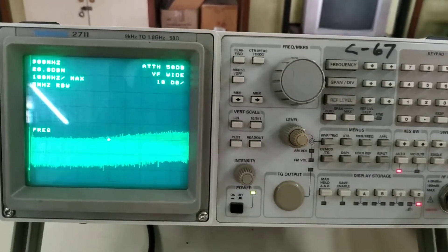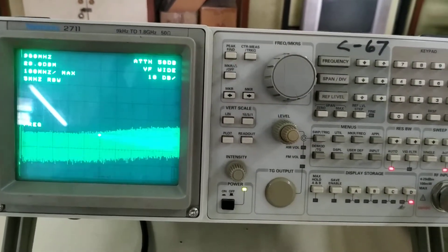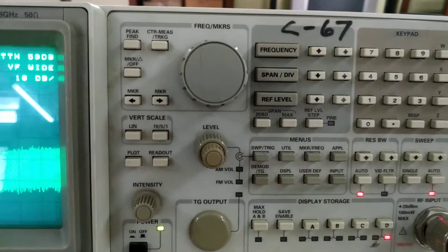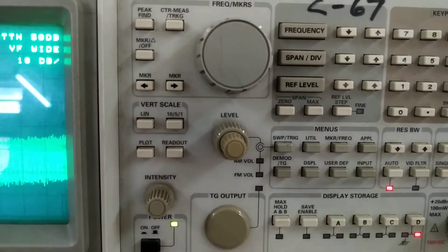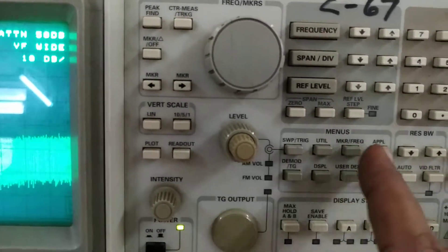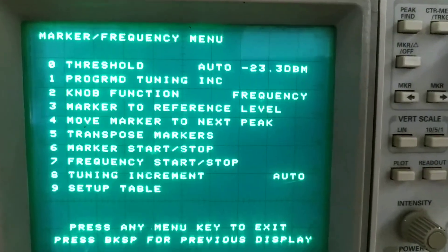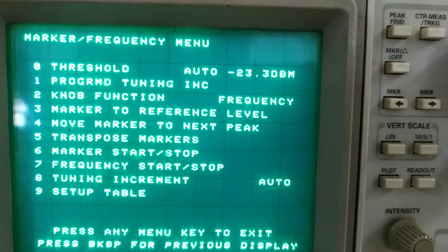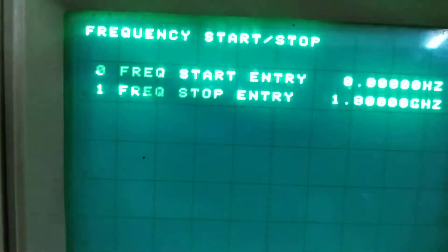Now we want to observe the spectrum, that means the frequency domain. For that purpose we will go to the menu. Within the menu we will consider the MKR FREQ button — that third button. This is the menu appearing there. Within this menu we will consider the seventh option, which is the frequency start/stop menu.